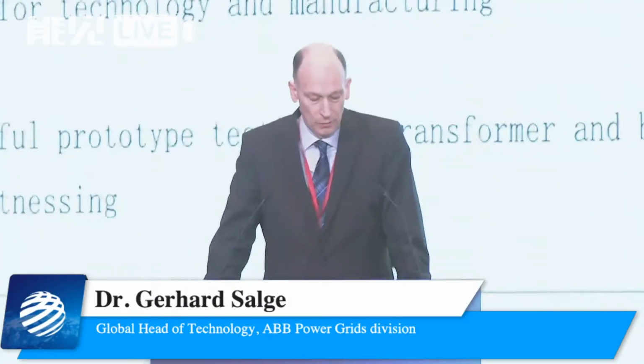As any good product development addressing a breakthrough starts with good technology development, in February 2011 State Grid and ABB met to define the first technology development parameters. We started from a target of 10.5 gigawatts, so 4,500 amps, and began by developing a prototype, manufacturing and testing it from the most critical components: the DC turret, the valve winding, and the cleats and leads. There was a significant need for power rating increase, because at that time the technology was at a level of 800 kV and 8 gigawatts.